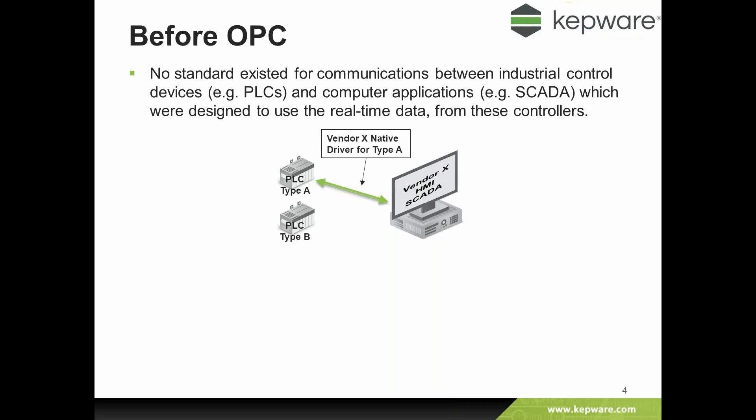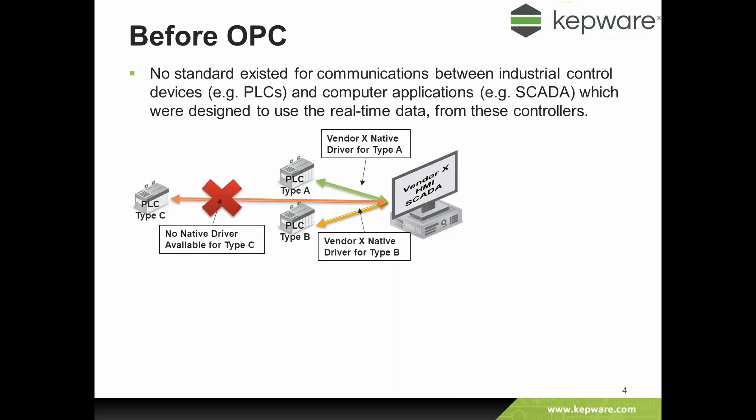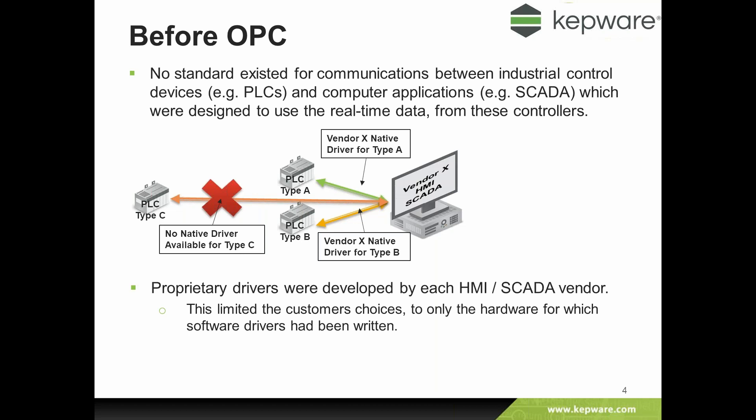In this diagram you'll see that the SCADA company is writing a native driver for PLC type A and another driver for PLC type B. But what happens if that SCADA or HMI software needed to communicate to a PLC type C, and the SCADA company hadn't written a driver for that? In effect, that software would not be able to communicate to those PLCs. The proprietary nature of drivers meant HMI and SCADA companies had to continually write new drivers, and if they didn't have the correct ones the customer wanted, their software was of limited appeal.